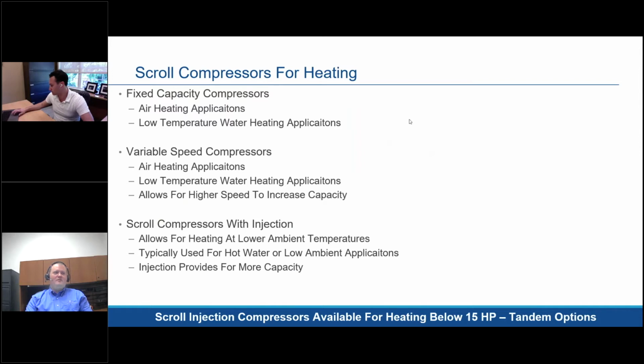This is a more detailed overview of the different heating options that we have today. Like I said, if you're making hot air, typically fixed capacity compressors and variable speed do well for air side heat pump systems. But if you want to make hot water, some type of injection, whether vapor injection, wet injection, or liquid injection, is really needed to get the hot water temperature up that you need due to the increased condensing temperatures.